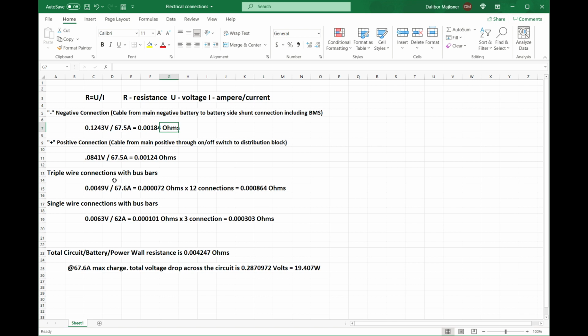At the 67.6 amp max charge that I achieved today per power wall, the voltage drop for one power wall would be 0.287 volts. Now, voltage times amperage will give us a power. That gives us a total power loss on all of these connections in one power wall equal to 19.407 watts. Now think about it, that's at 67.6 amps. Now we have to guess some kind of average power loss during all times of the day. I want to guess that it's around 7 or 8 watts.